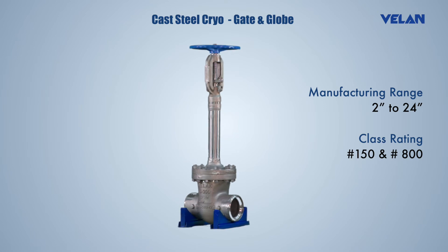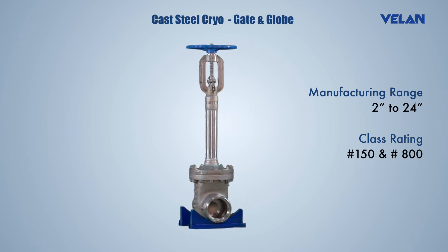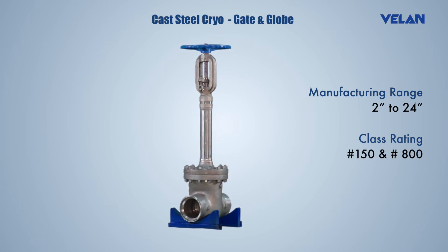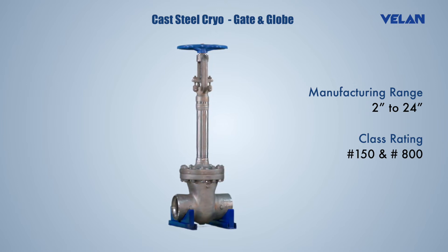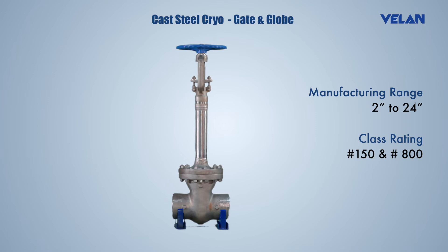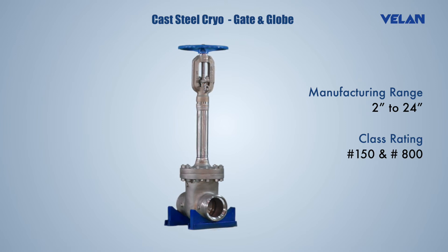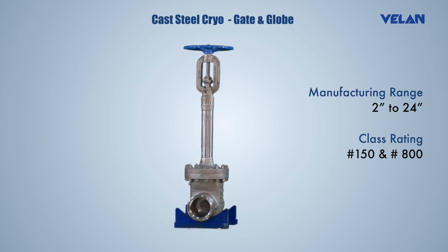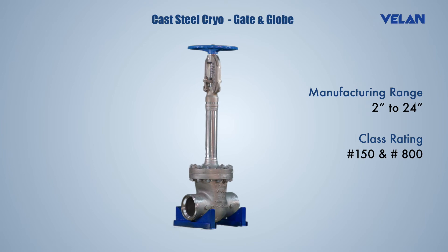Velan has a range of cryogenic valves offering greater impact strength, minimal heat loss, and protection against corrosion to withstand temperatures as low as minus 196 degrees Celsius, qualified to international standards. Extended bonnets with sufficient gas column length keep the stem packing away from cold fluid. Valve stems offer high toughness at extreme low temperatures, excellent low friction and galling-free movement.